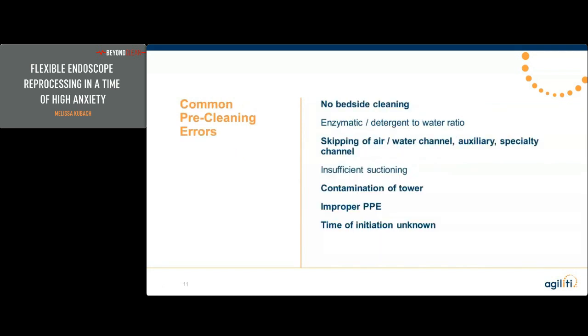Common errors: the very first one on the list is no bedside cleaning at all. For anyone in GI, you're probably looking at each other wondering what that means, because GI really does have a good handle on bedside cleaning overall. The only area I see issues is skipping steps related to specialty models, like balloon channels, elevator flushing channels, and some multi-stage suctioning steps required at the end of the case for linears and radials. So otherwise, GI is very good, but no bedside cleaning is really an issue in the ORs.